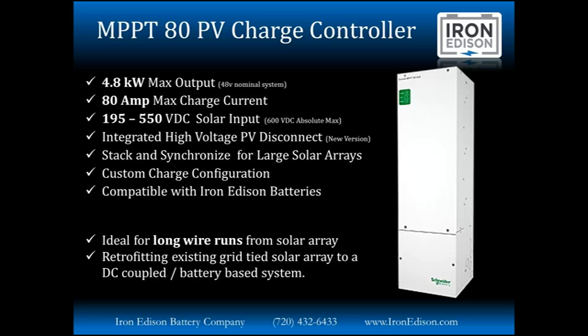Also, if you have an existing grid-tied solar array that's currently using a grid-tied string inverter, and you want to upgrade or retrofit it to a DC-coupled battery-based system, this could be a direct replacement for a typical grid-tied string inverter. The voltages and current typical with an array like that will line up perfectly with the MPPT 80, so you don't have to get up on the roof and rewire the array or anything of that nature. Literally just take the string inverter off the wall, put the MPPT 80 in place, and you're good to go.